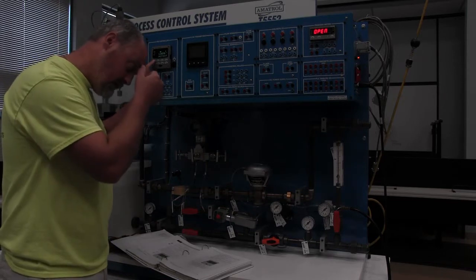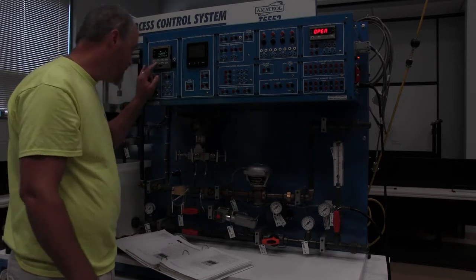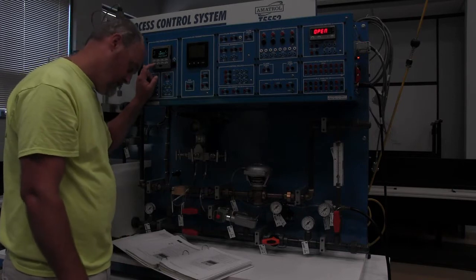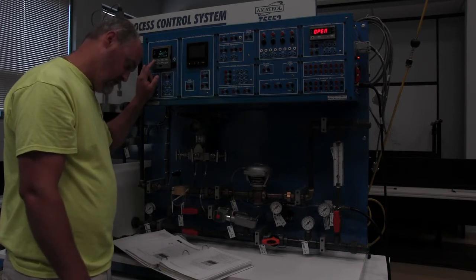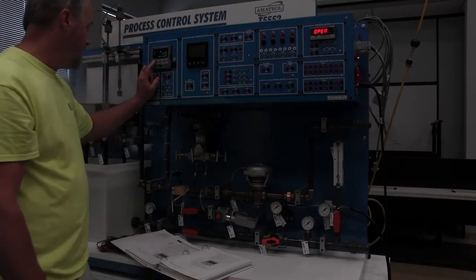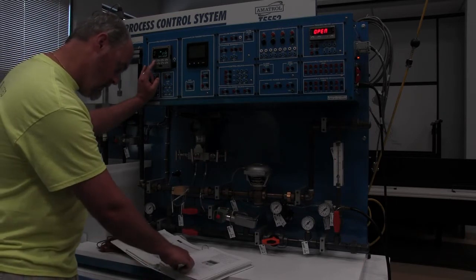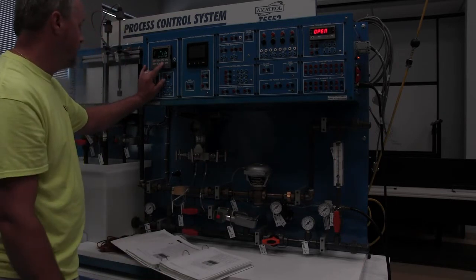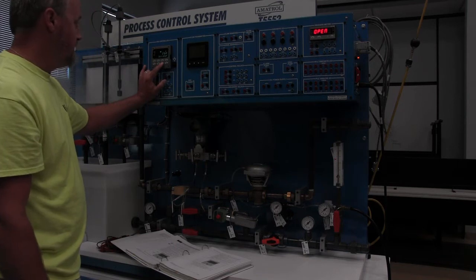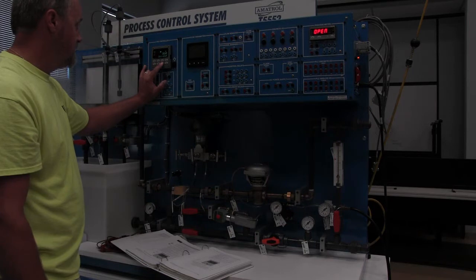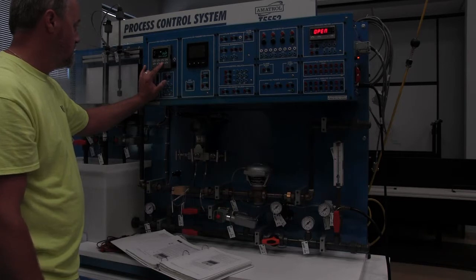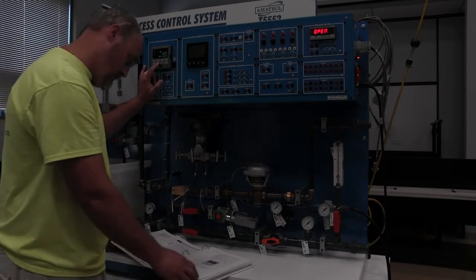X meter is linear. Use up down keys to change the setting to square root. Square root. Press the function loop key to in1 high. In1 high, we're going to set to 25, which right now it's at 27.7. So we're just going to go down to 25.0. Alright, we're now at 25.0.